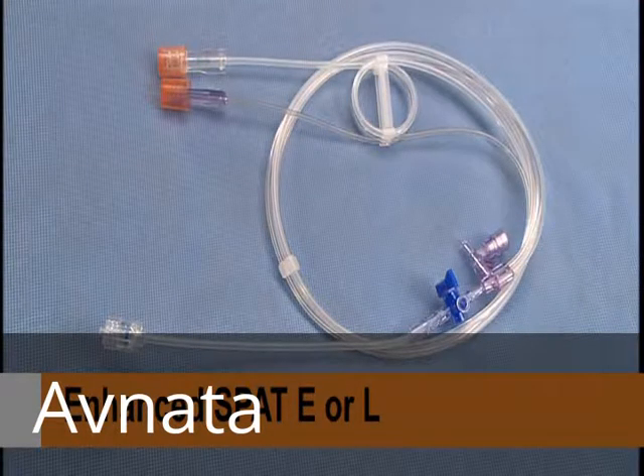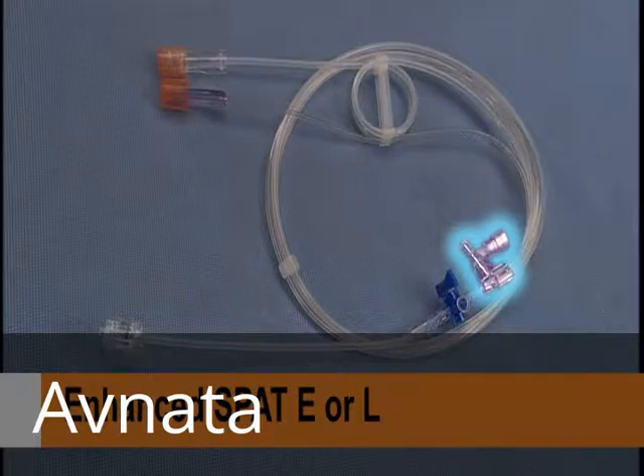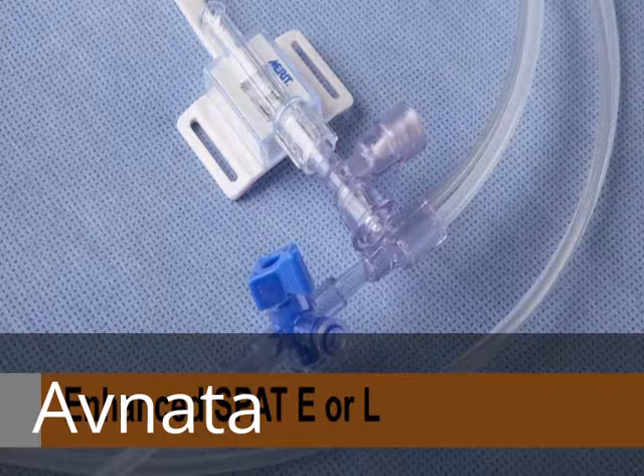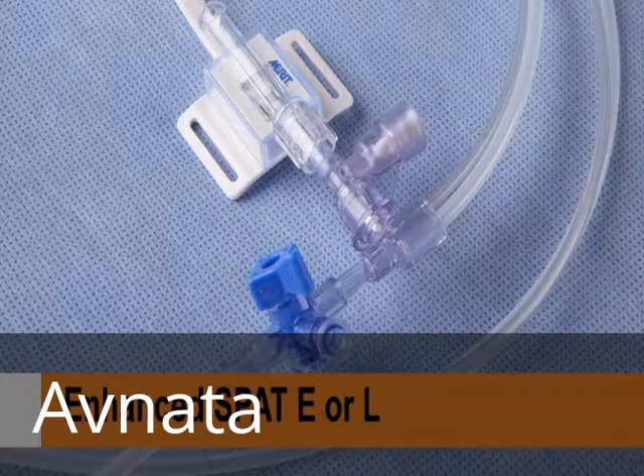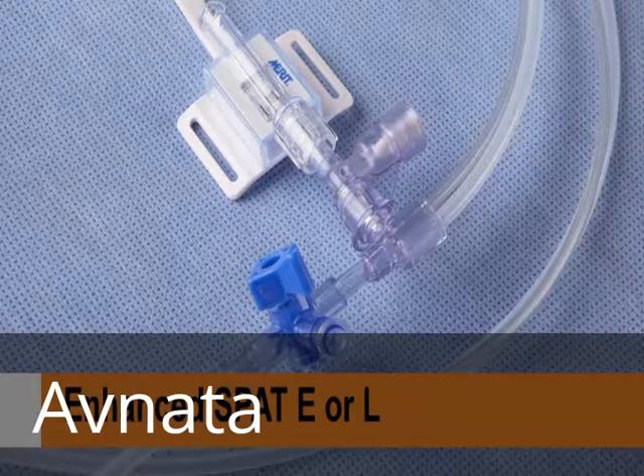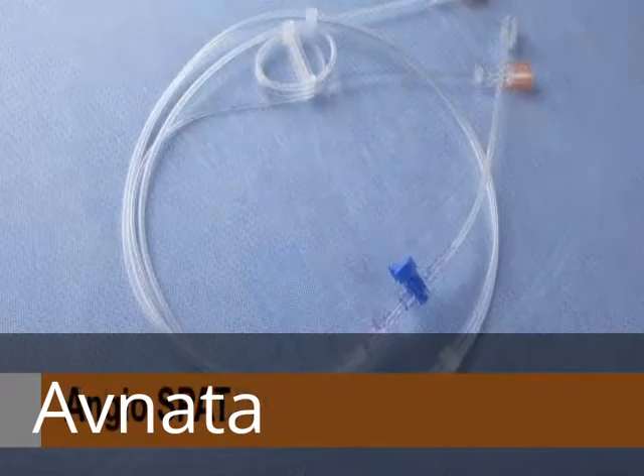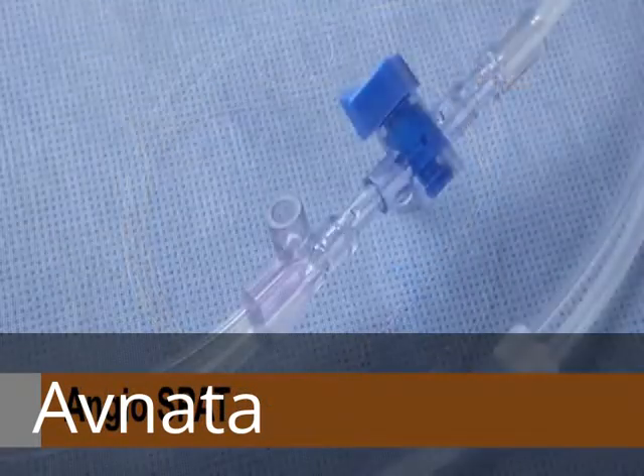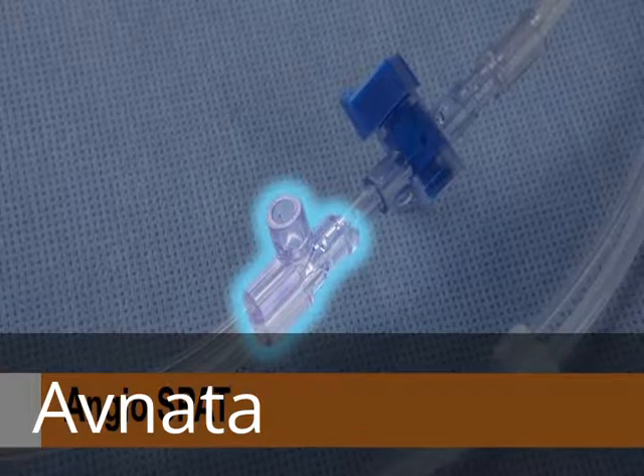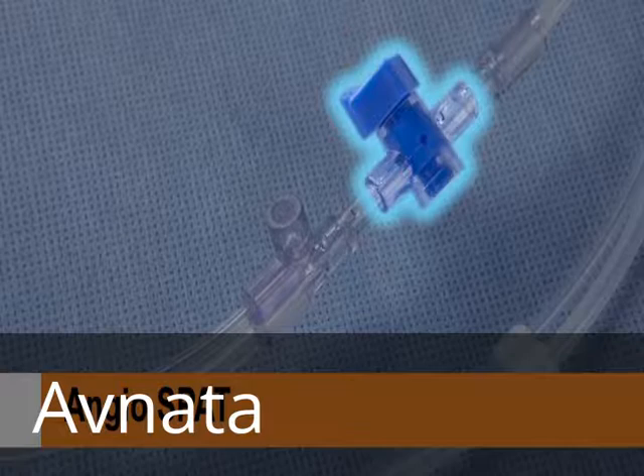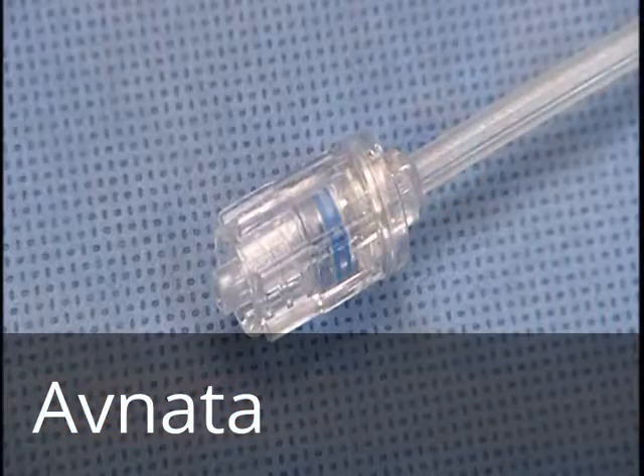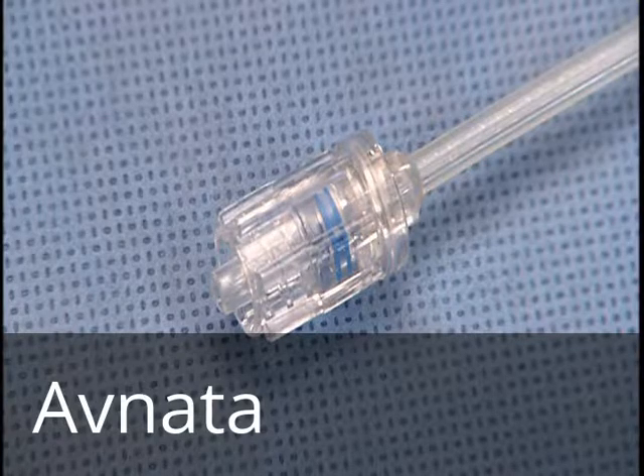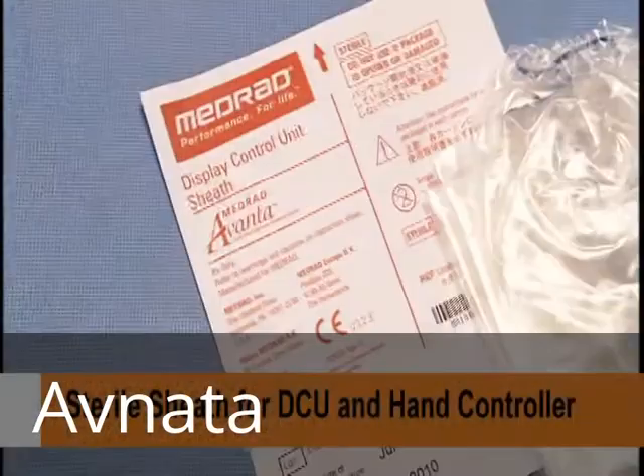Enhanced and Long SPATs contain an automated pressure isolation valve assembly, or PIV, which protects the attachable transducer and aids in hemodynamic pressure monitoring for instantaneous waveform transmission. The Angio SPAT does not contain a hemodynamic port and is used when a procedure does not require a transducer. The waste port stopcock can be used either as a waste port or for medication delivery. The rotating luer aids in catheter connection and manipulation.